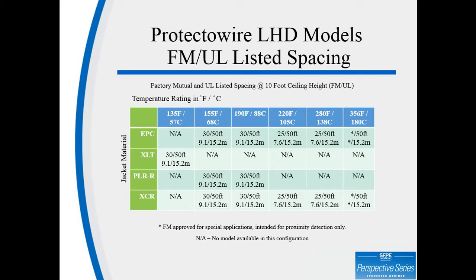If you follow along on this particular slide and on this chart, you'll see that we go all the way up to 356. The 356 is listed and approved by FM for proximity detection. In other words, you put this particular detector on the apparatus you're trying to protect, for instance, transformers or conveyors. UL has given it a listed spacing of 50 feet for open area.